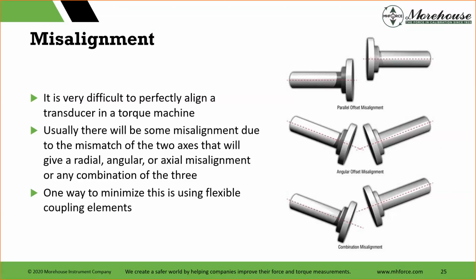However, that increases your risk and your measurement traceability, depending on who's doing the cal. Maybe the one lab misaligns the cell. They think they're operating at these really low uncertainties. They're actually 10 times higher. Then they do another transfer standard that then is used for the wrenches. All of a sudden, you could start eating up large error sources, especially when you get into these different types of misalignment.